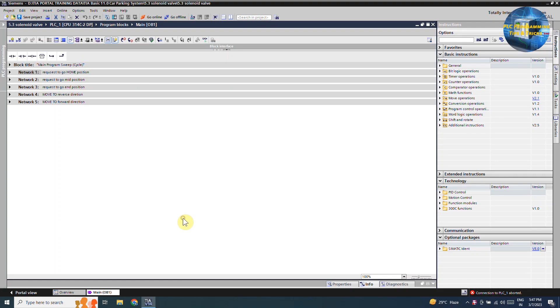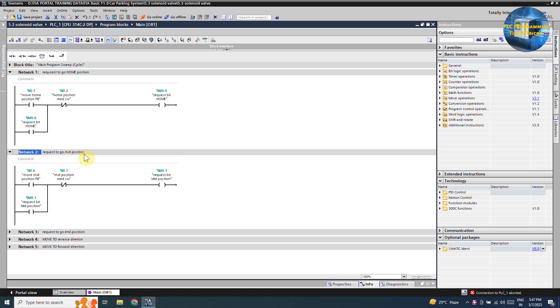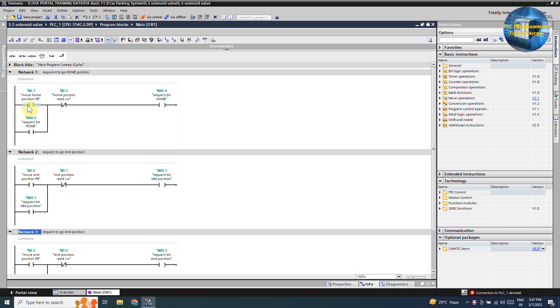Now let's go to the TIA portal software and see the ladder logic. In network 1 we have the logic to make a request to go to the home position. In network 2 we have the logic to make a request to go to the mid position. In network 3 we have written the logic to make a request for the end position. In network 1, when we press the home position push button i0.7 and the cylinder piston is not at the home position reed switch i0.2, it will latch on the request bit home.